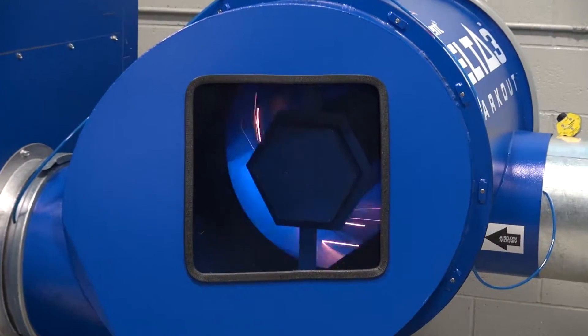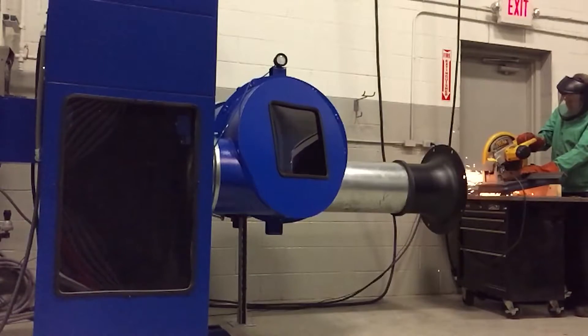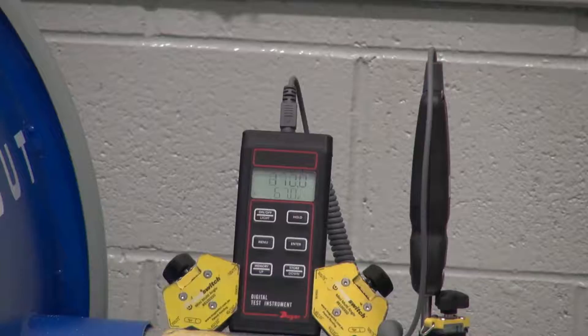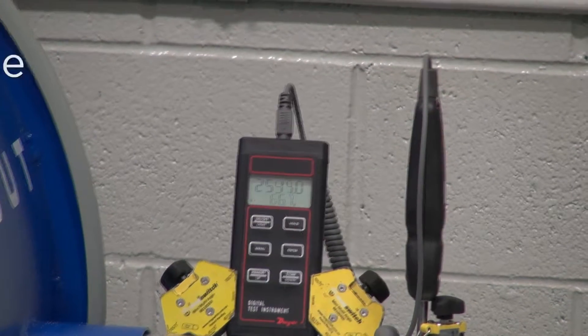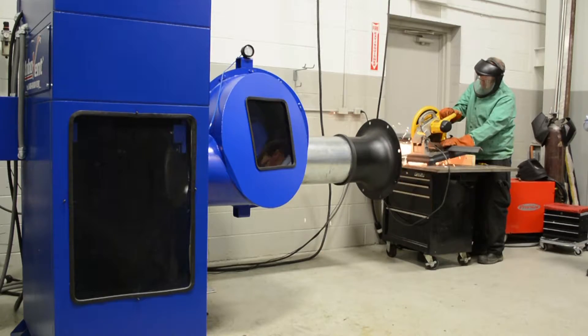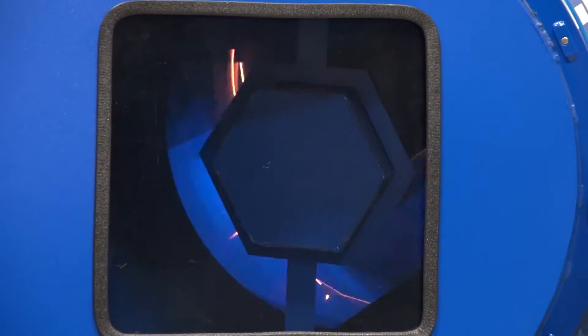The patent-pending Delta III technology uses centrifugal action to drive sparks and embers against the outer wall of the device, stripping off the thermal envelope that surrounds them so that they are rapidly cooled and extinguished. At the same time, high air velocities are maintained on the surfaces inside the device, eliminating particulate deposits, so the unit is constantly cleaning itself.